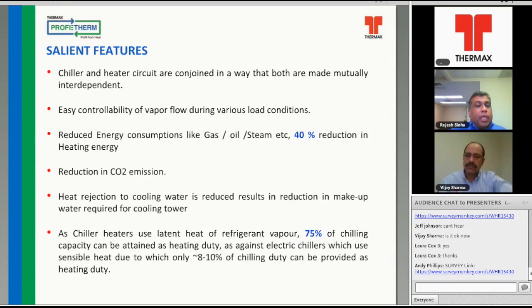The salient features for this particular product, which is unique and can be very widely used in the food industry, because in this kind of product the cooling and the heating load have to occur simultaneously, and that is quite possible in the food industry. So a chiller and heater circuit are conjoined, and they are mutually interdependent, so you can't have one without the other. We do have the other either-or product, which is the standard chiller heater. But talking about the high-efficiency chiller heater, both the utilities have to be simultaneously utilized from the absorber. But that's the only constraint.